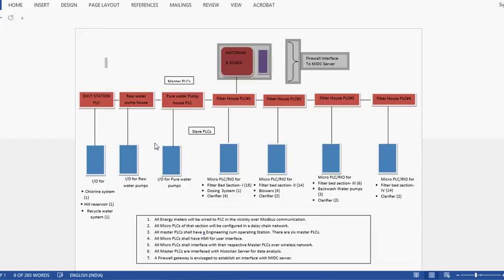Automation of this plant includes 7 master PLCs covering the raw water system, pure water system, EHVT station, and one master PLC for each filter stage. There are four stages of filters. A historian is interfaced with all master PLCs where process data is collected and analyzed. The historian interfaces with the MIDC server to make historical and online data available.